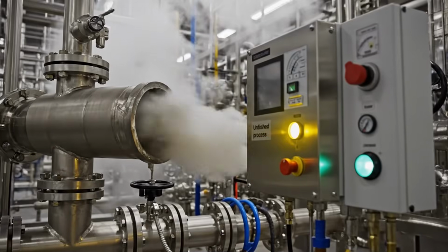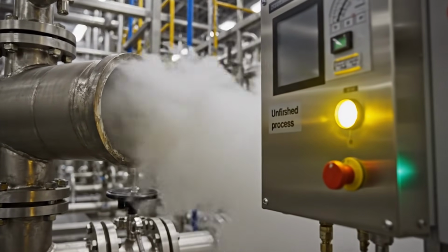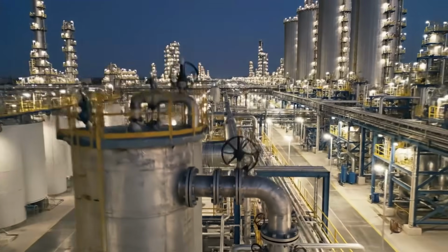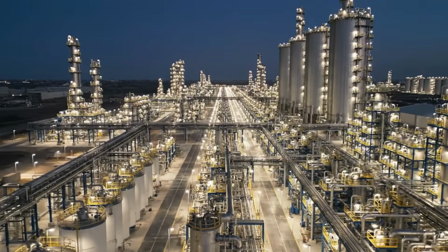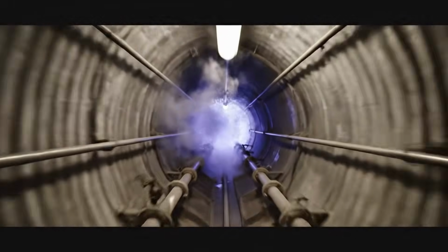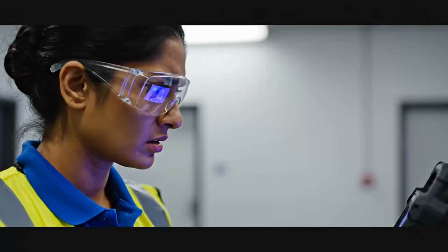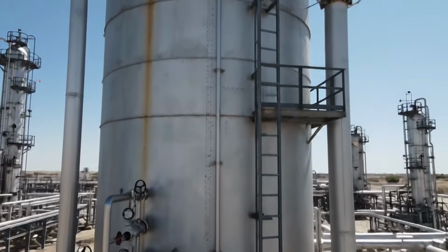Its removal is indispensable. To do this, the gas passes through sweetening units where it comes into contact with amine solutions. These solutions selectively absorb acidic gases, allowing the methane to proceed with much higher purity. The amines are then regenerated in another section of the plant, releasing the captured compounds and returning to the operational cycle. The treatment of hydrogen sulfide does not end with its separation.